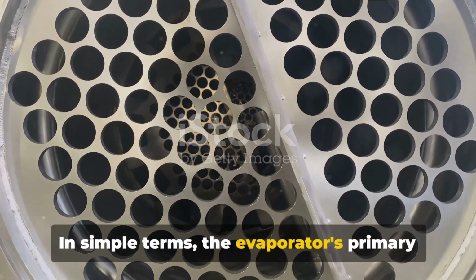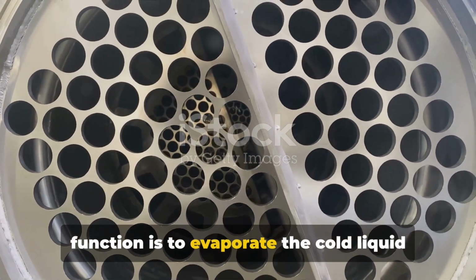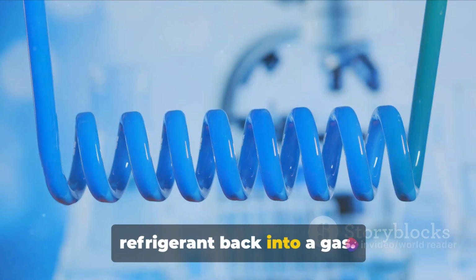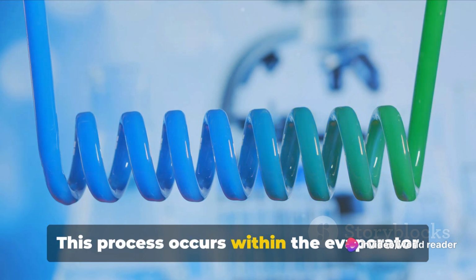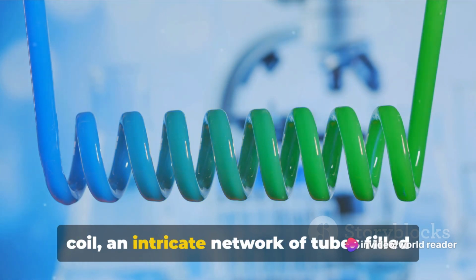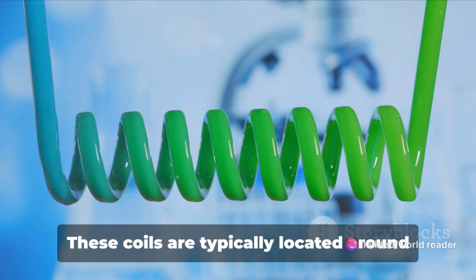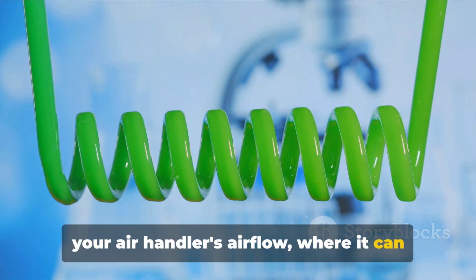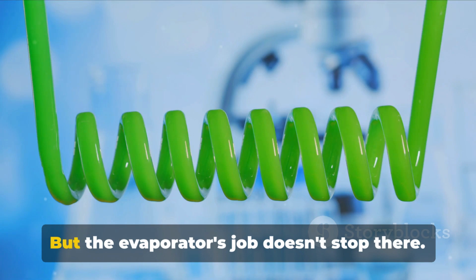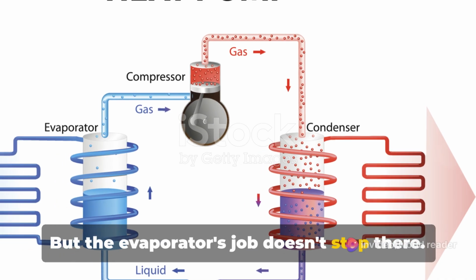In simple terms, the evaporator's primary function is to evaporate the cold liquid refrigerant back into a gas. This process occurs within the evaporator coil, an intricate network of tubes filled with refrigerant. These coils are typically located around your air handler's airflow, where it can do its job most effectively. But the evaporator's job doesn't stop there.